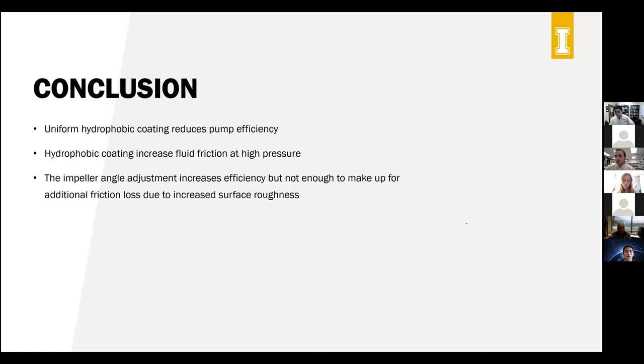So to sum up, we found that uniform hydrophobic coating reduces the pump efficiency and that the hydrophobic coating increases the fluid friction at high pressure zones, and that the impeller angle adjustment increases efficiency, but not really enough to make up for the additional friction loss due to the increased surface roughness. And so with that, I think we'll take questions.